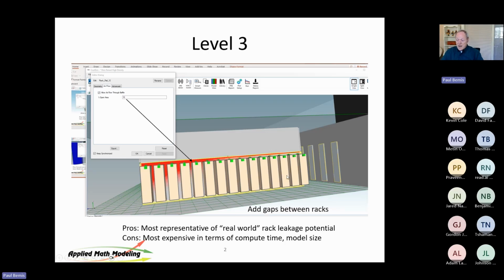Now I put a gap between the racks, and I made these racks a little bit smaller than normal. In other words, if the rack is 2 feet wide, I'm making it 19 inches because I want 3 inches on either side of that rack to be leaking. So here in this design, what I've done is gone to one more level of complexity, one more level of detail, where I'm actually modeling the rack rail in addition to the leakage around the rack using one surface called leakage, right? Because we don't know in the real world where the leakage is. It could be around the servers. It could be the rack rail, could be top, could be bottom, could be where it intersects the cabinet, intersects the containment. All of those surfaces could leak. You could define them individually and try to put those in, but that's complex. What we do instead, to save time and be more efficient, is represent it with one surface.